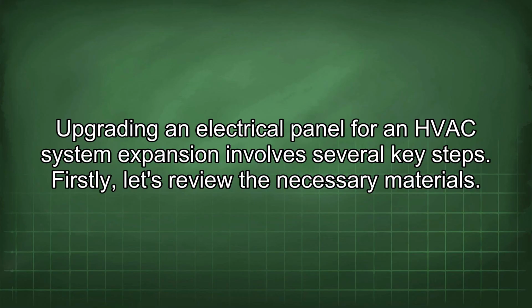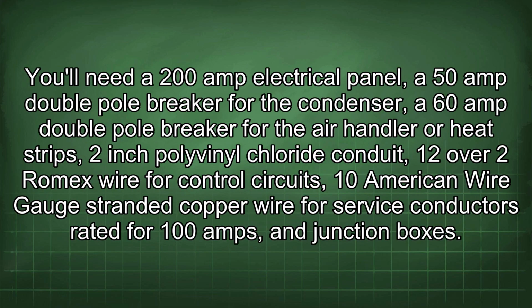Upgrading an electrical panel for an HVAC system expansion involves several key steps. Firstly, let's review the necessary materials. You'll need a 200 amp electrical panel, a 50 amp double pole breaker for the condenser, a 60 amp double pole breaker for the air handler or heat strips, 2-inch polyvinyl chloride conduit, 12/2 Romex wire for control circuits, 10 American wire gauge stranded copper wire for service conductors rated for 100 amps, and junction boxes.